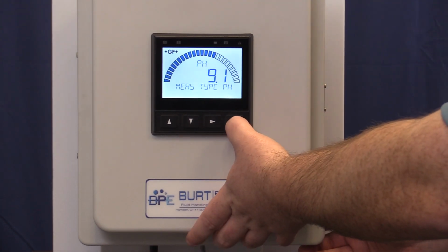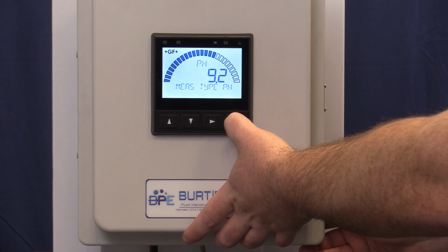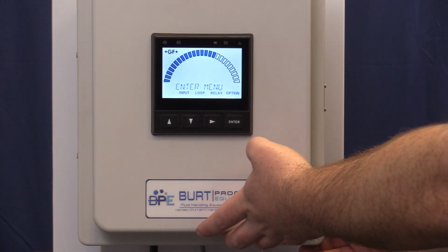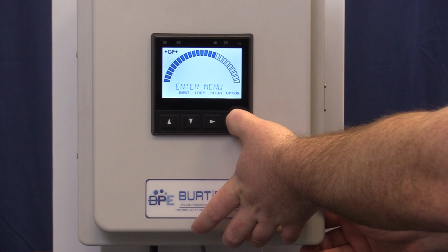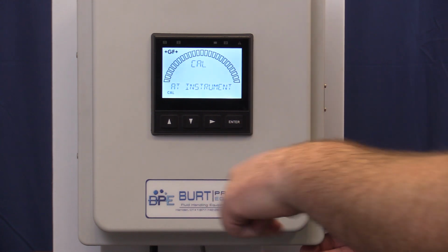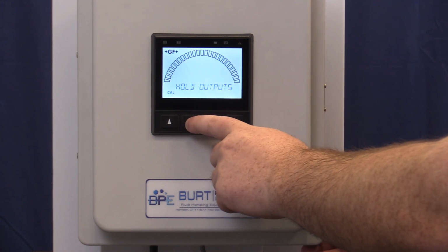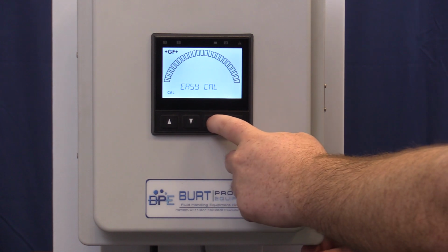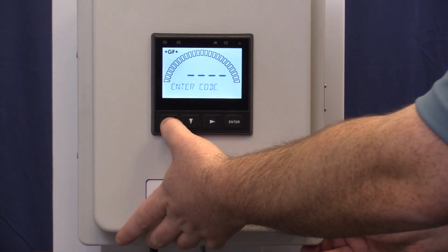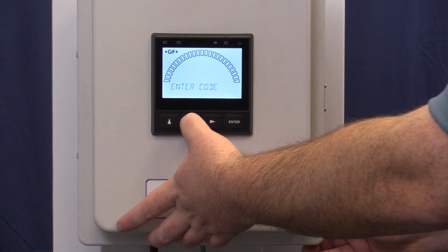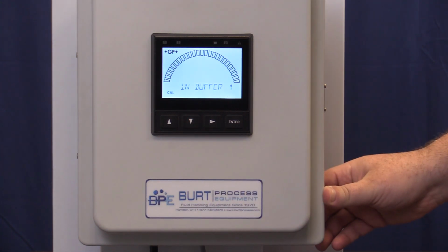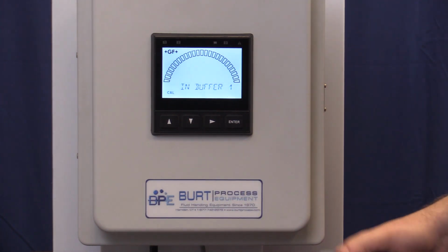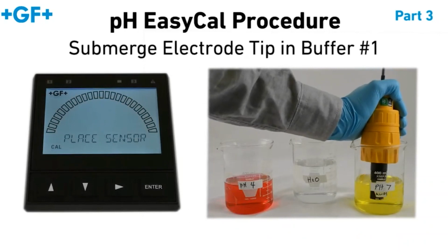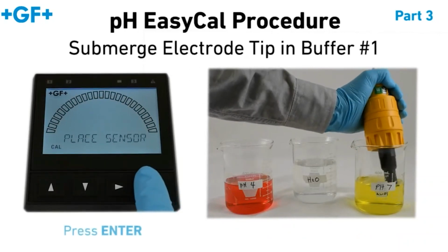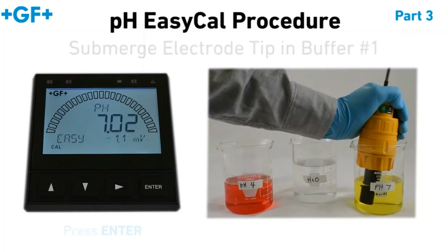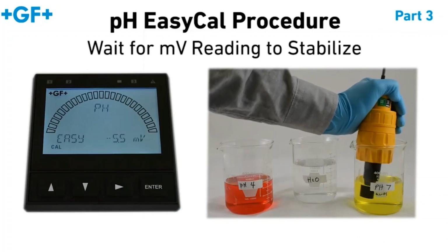So if we press and hold enter for 3 seconds, it brings us to the menu screen. We can press enter for calibration. So then we want to go down to EasyCal. Enter the passcode, up, up, up, down. So then what you want to do is hold this in solution, and then press enter. And then you would want to do the same thing in buffer 2.